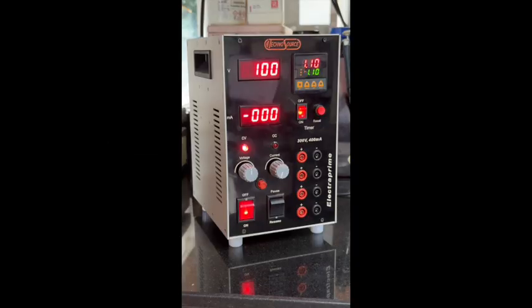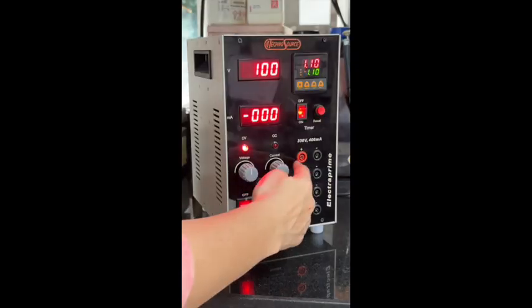Indication 4. Instrument is on but current display shows 0. In this, the main switch is illuminated. The light on CV or CC indicator is on and both displays are on. The voltage display shows desired voltage but current display shows 0. This can happen due to 8 common reasons. Cause 1. No load connected.